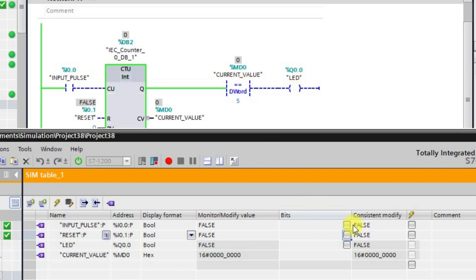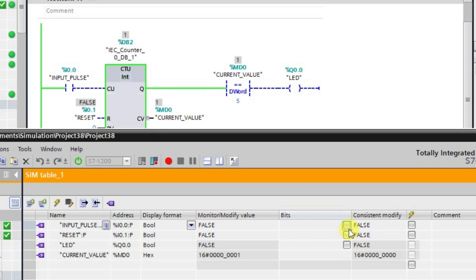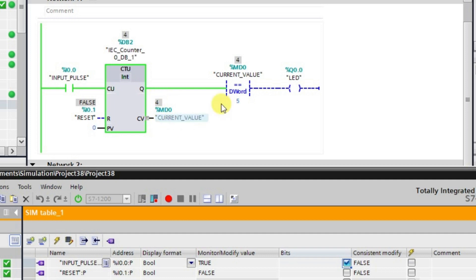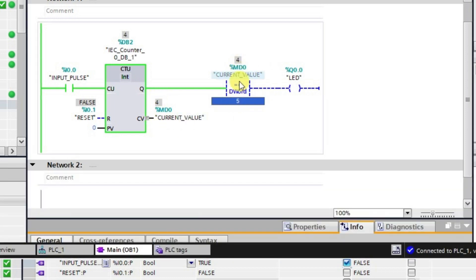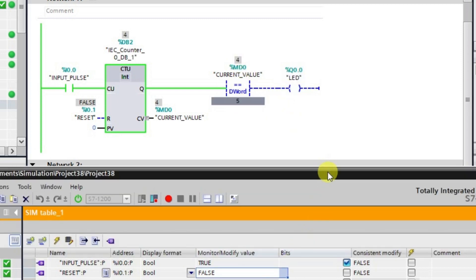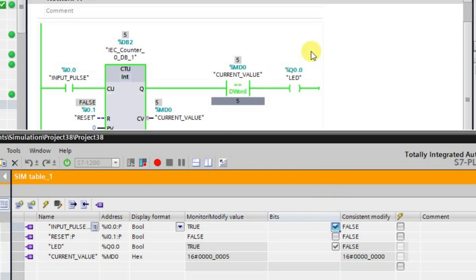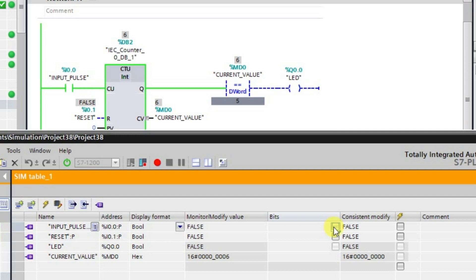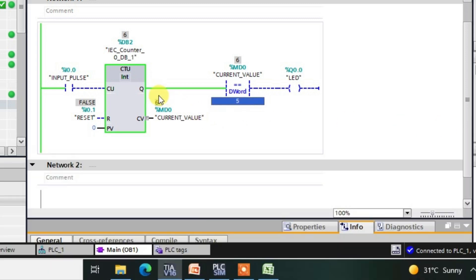As we give pulses, the counter value changes and is stored in MD0. That same value is fed to the comparator and compared with 5. When the fifth pulse is given and the current value equals 5, the output goes high. If the value is 6 and the preset is 5, the values are not equal and the output returns to the low state — this is how the equal to comparator works.